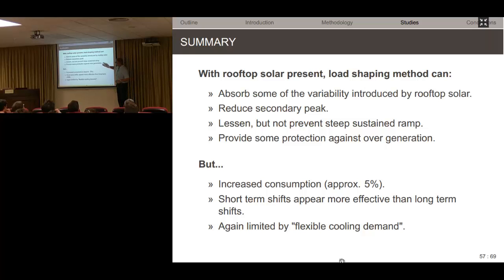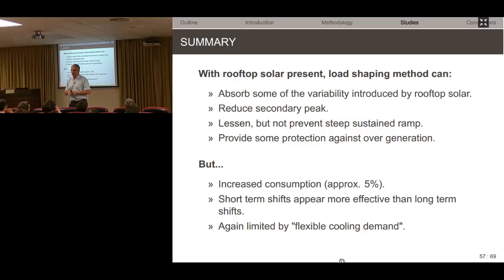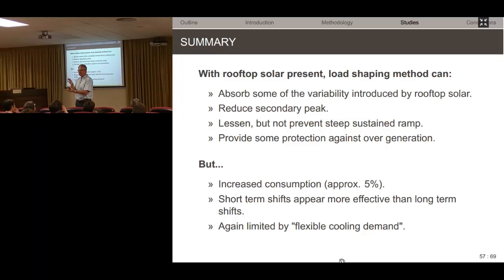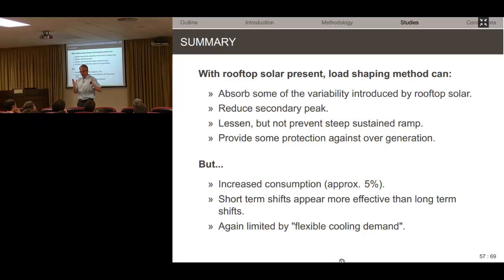So these are good things, but we have an increased consumption of about 5%. We seem to be able to provide short-term shifting on the order of a few hours more than long-term shifting, simply by virtue of the fact that the homes are lightweight. If you pre-cool a building 5 Kelvin from the set point for a number of hours and then let go, this stored energy doesn't help you through a day's worth of operation, but a few hours. That's why we see this.